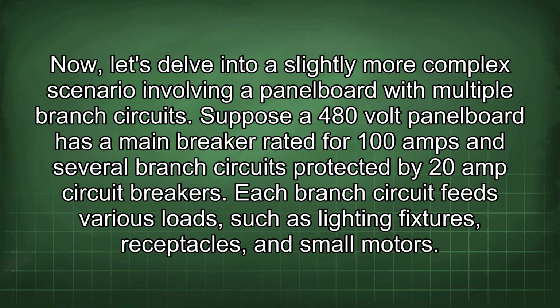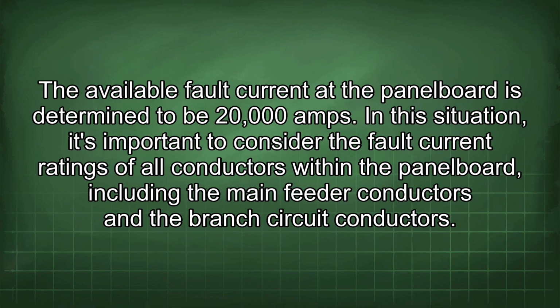Each branch circuit feeds various loads such as lighting fixtures, receptacles, and small motors. The available fault current at the panel board is determined to be 20,000 amps. In this situation, it's important to consider the fault current ratings of all conductors within the panel board, including the main feeder conductors and the branch circuit conductors.